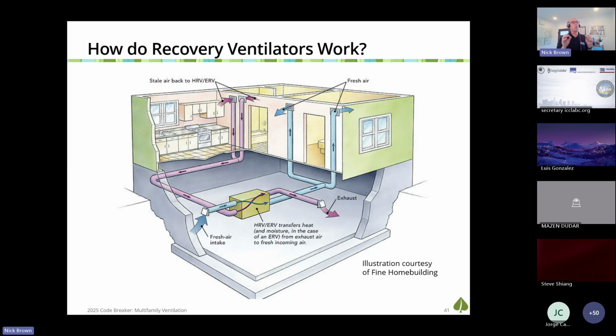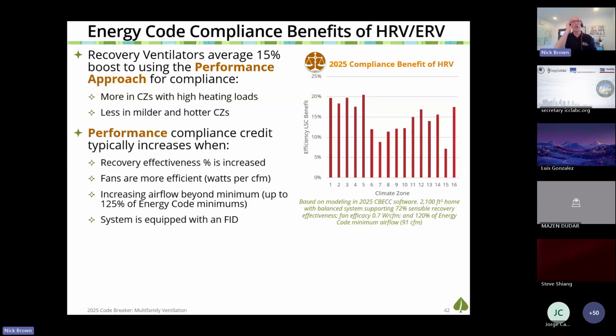So in most cases, these require 2 penetrations through the building envelope, one for the fresh air and one for the exhaust. And there needs to be some provision for that MERV 13 filter on that fresh air intake stream. I did a quick chart of the compliance benefit of recovery ventilators in our 2025 software. I show it by climate zone in this chart here. So you can see it's an average 15% boost to your performance compliance metrics across climate zones, more in cooler climate zones, 1 through 5, 12 and 16. And you can juice that compliance credit with better recovery effectiveness, more efficient fans, and a little extra airflow, or equipping your system with an FID.